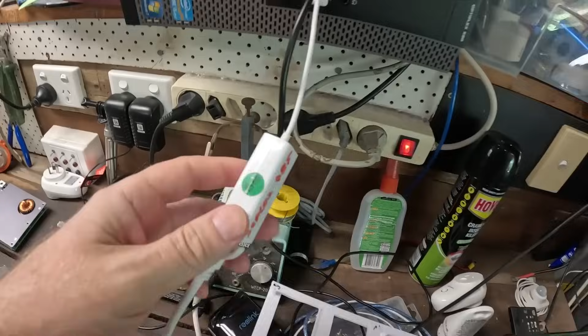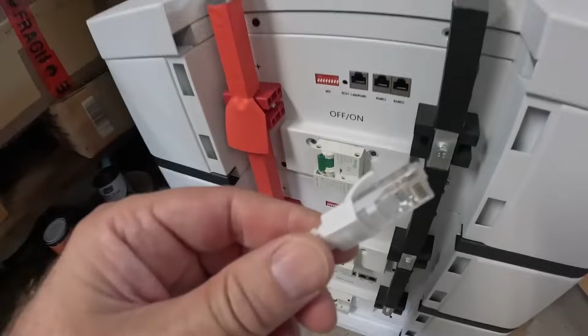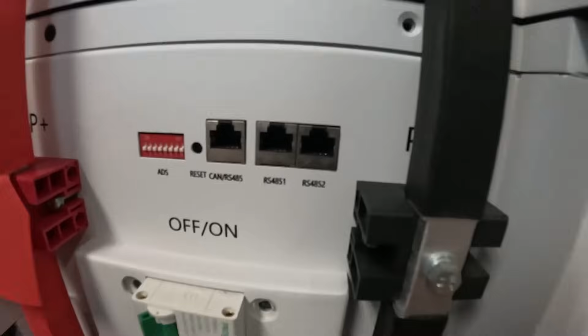All we need now is the Seplos RS485 adapter to USB, but you can also use any kind of USB to RS485 adapter, it doesn't need to be from Seplos. When you connect the other end of your LAN cable to your BMS, you can only use the RS485 port 1, not the RS485 2 port. It will not communicate on this port, only on port number 1.